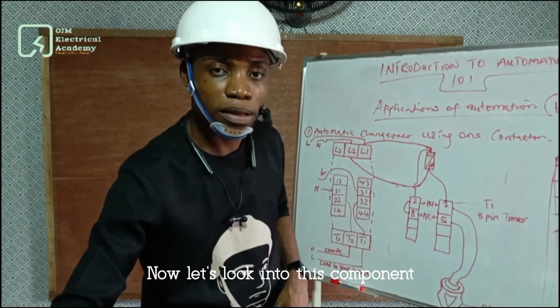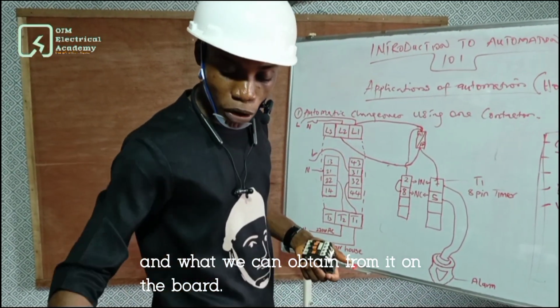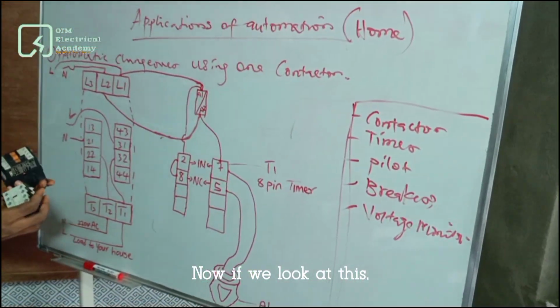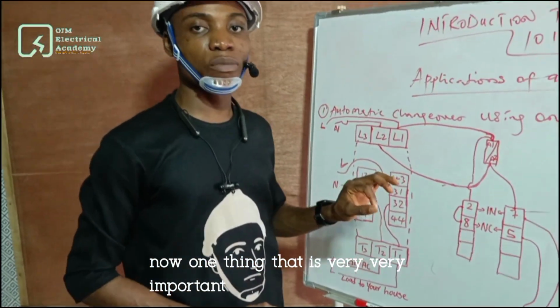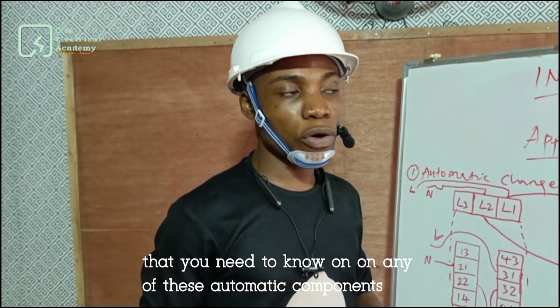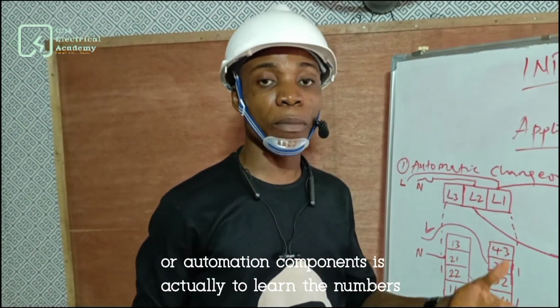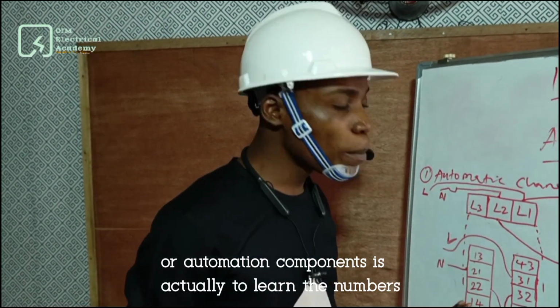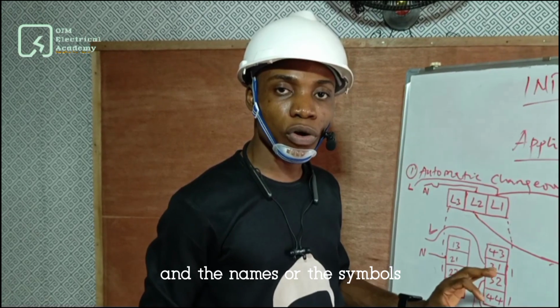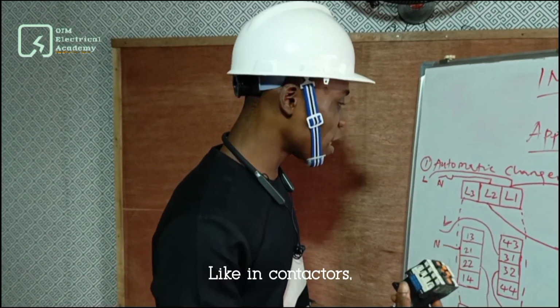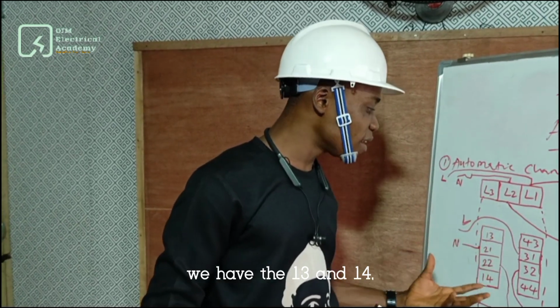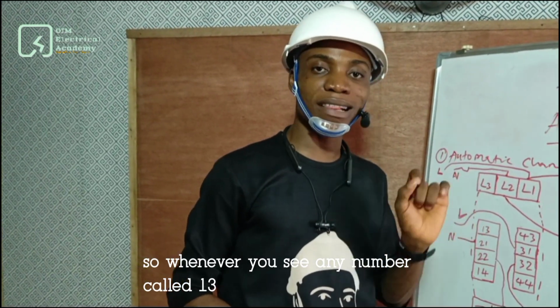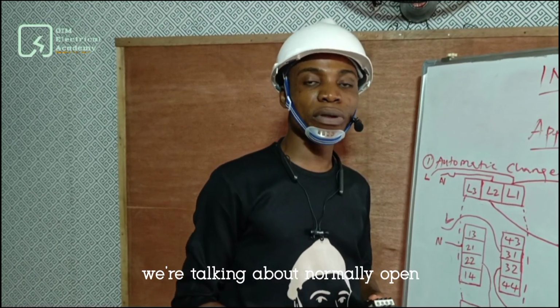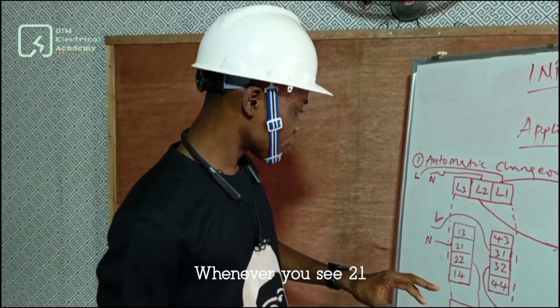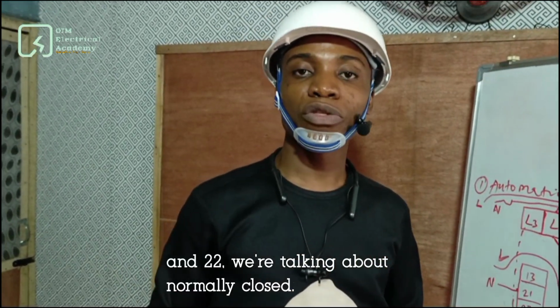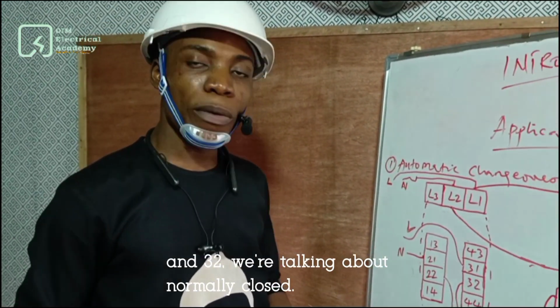Now let's look into these components and what we can obtain from them on the board. One very important thing to know about automation components is to learn the numbers, names, and symbols used. For contactors, we have 13 and 14, which refer to normally open contacts. Whenever you see 21 and 22, we're talking about normally closed, and 31 and 32 also refer to normally closed.